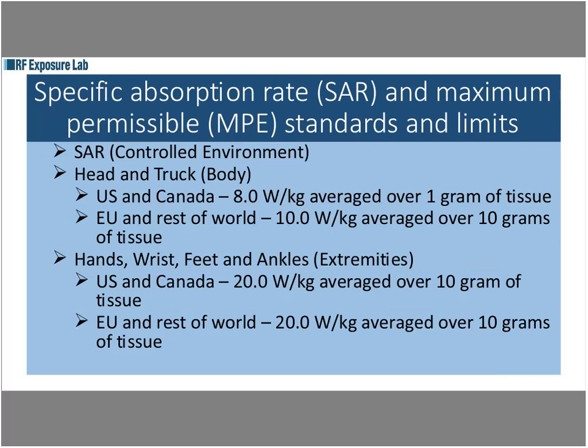And then for the SAR, for the controlled environment, you've got the head and the trunk, or the body. The US and Canada is 8 watts per kilogram averaged over 1 gram of tissue. Again, this is for the controlled environment, not the general population. And then the EU and the rest of the world uses 10 watts per kilogram averaged over 10 grams of tissue. Now, the rest of the world includes pretty much everybody except Korea. Korea tends to follow the FCC limits, even though they use the EU test methodologies. So there's a bit of a disconnect there. They're the only country that actually uses the 1.6 and 8 watts, rather than where the rest of the world uses the 2 and 10.